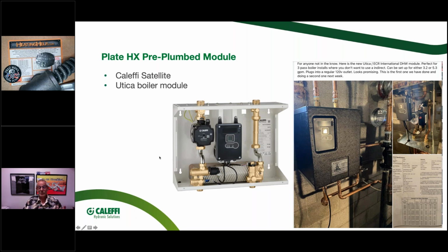What he found out, and this was interesting, it was put in on an older building that had previously had some rubber tube on the job, and it actually fouled up the A side of the heat exchanger, the boiler side. When he tipped it over and shook it, all these little granules of black, brownish chunks of something came out of it. So you assume it's always the B side, the domestic water side, that's going to foul up, but in this case it was actually the boiler side, the A side of the plate heat exchanger, that had fouled up to the point where they were getting half the amount of domestic hot water that they expected.